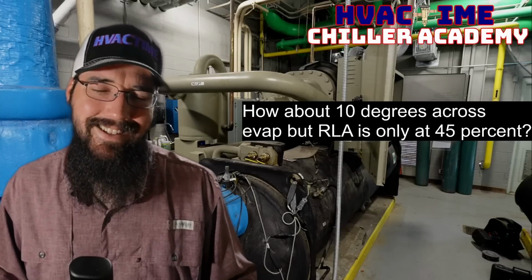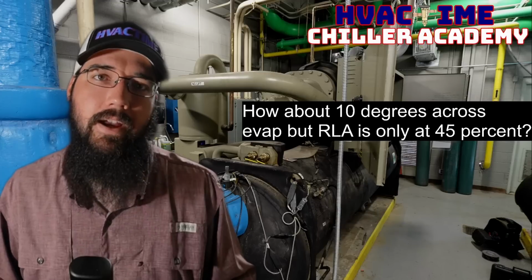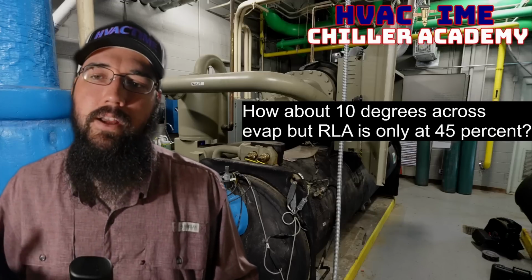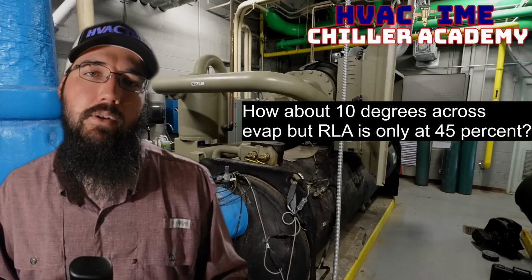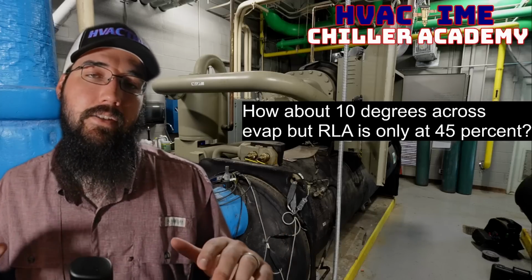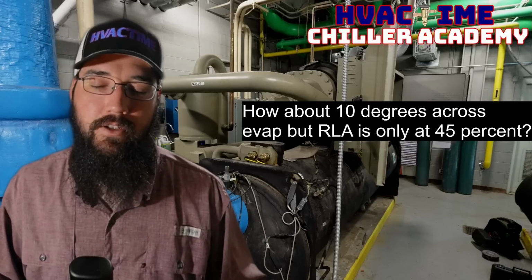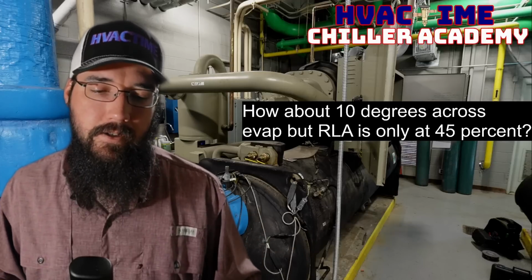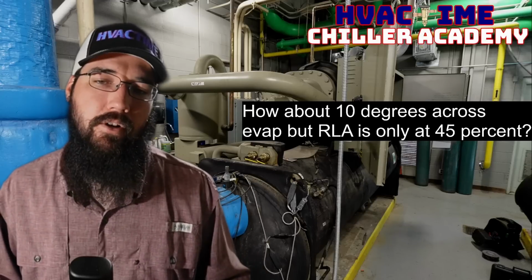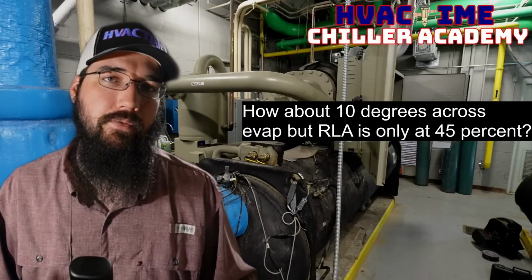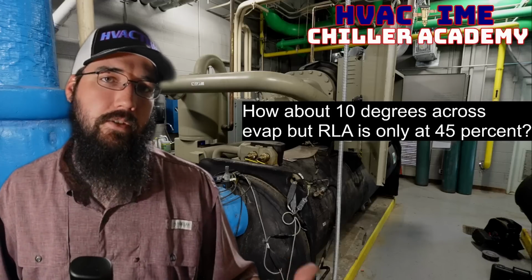Now, that is in the context of I know for sure that my GPM is correct, my refrigerant charge is good, my tubes are good. That's in the context of all these other variables that will impact that differential temperature being in a good condition. It's very, very important.